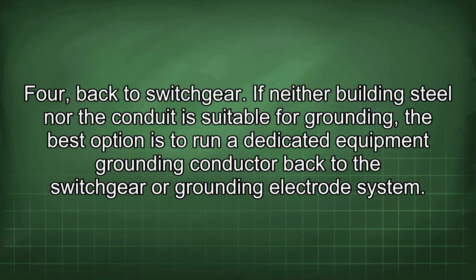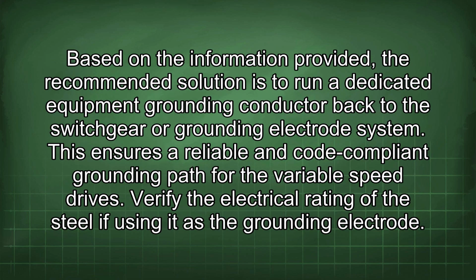4. Back to switchgear. If neither building steel nor the conduit is suitable for grounding, the best option is to run a dedicated equipment grounding conductor back to the switchgear or grounding electrode system. Based on the information provided, the recommended solution is to run a dedicated equipment grounding conductor back to the switchgear or grounding electrode system. This ensures a reliable and code-compliant grounding path for the variable speed drives.